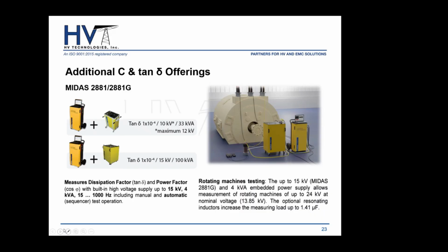I mentioned earlier about motors and generators and having higher capacitance devices or specimens. For that, we also offer the MIDAS 2881 or 2881G. With the MIDAS 2881, you can include an external resonating inductor, which will let you test up to 1.41 microfarads. So it really opens up the range to include your rotating machines. And the 2881G is specially designed for generators because it will go up to 15 kV, which is perfect for 24 kV class voltages. So we have that also.